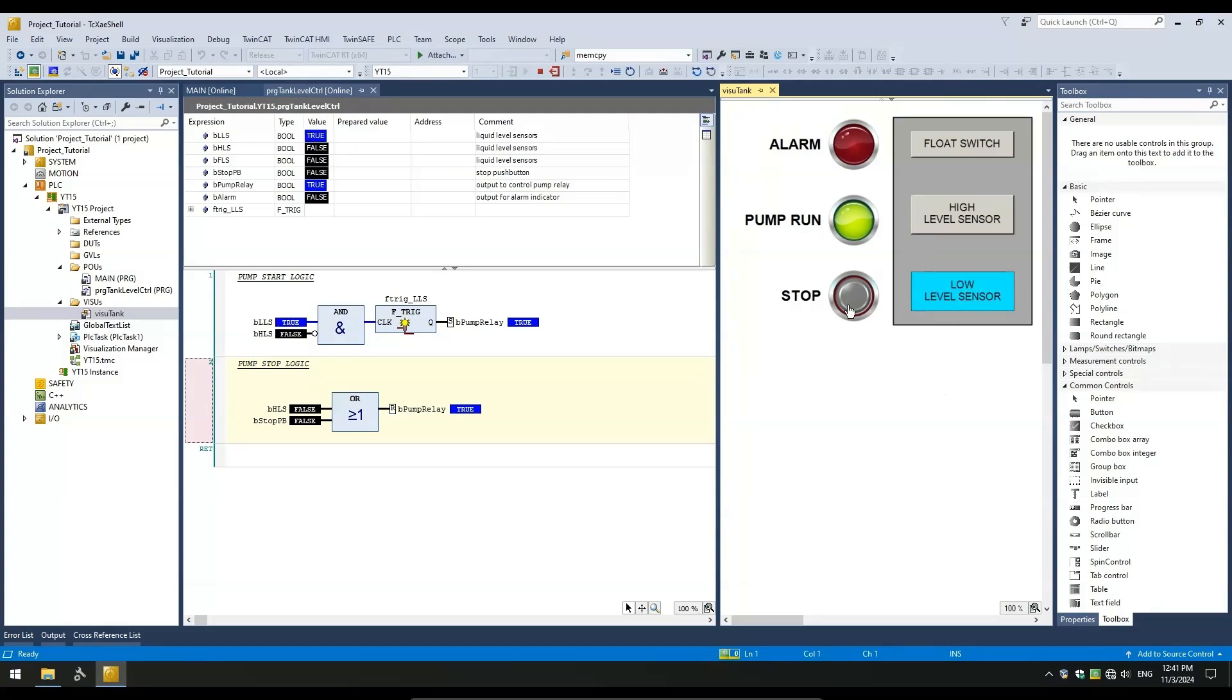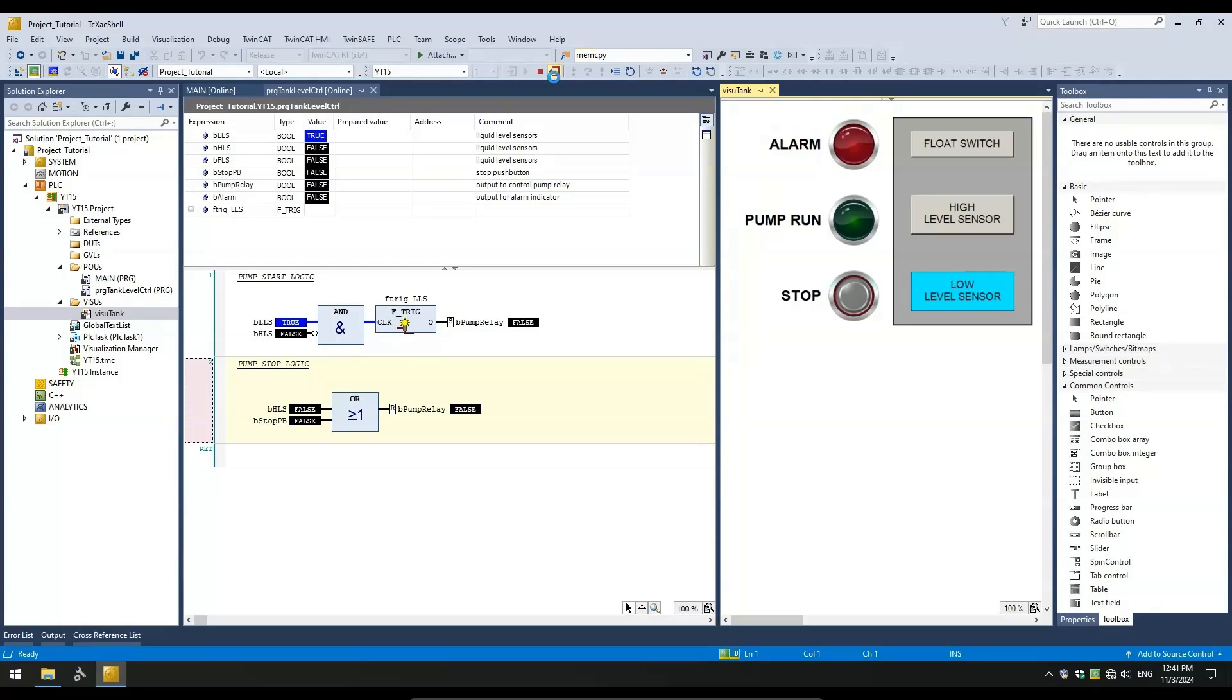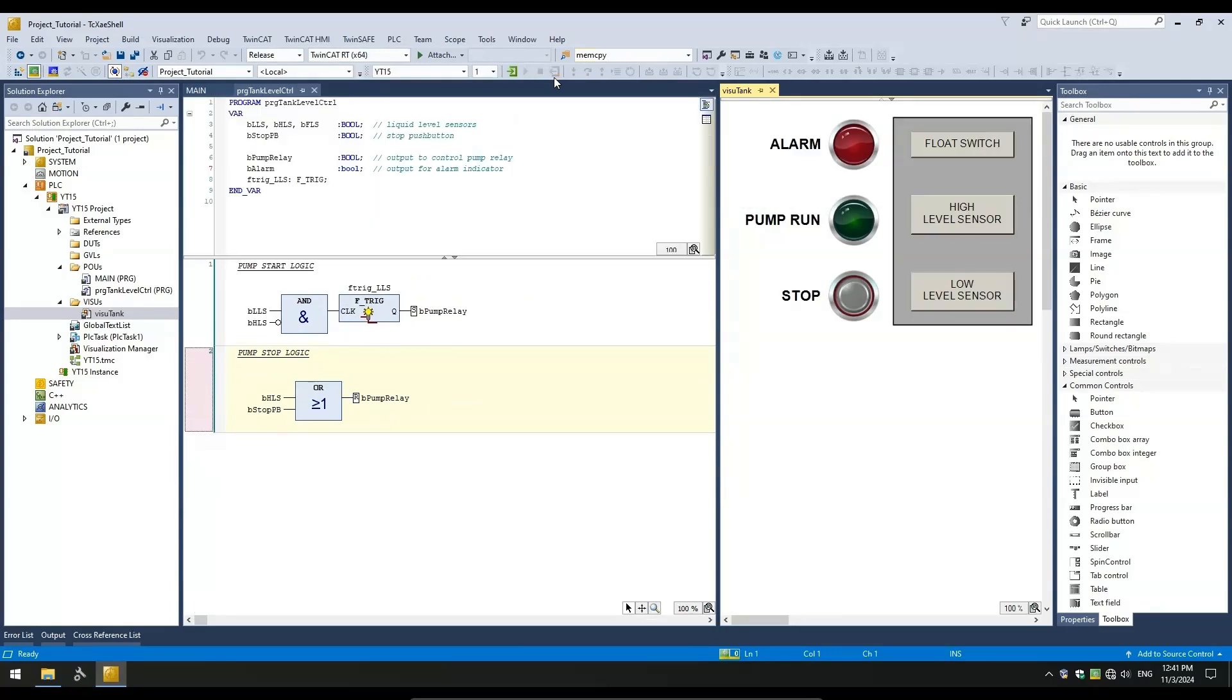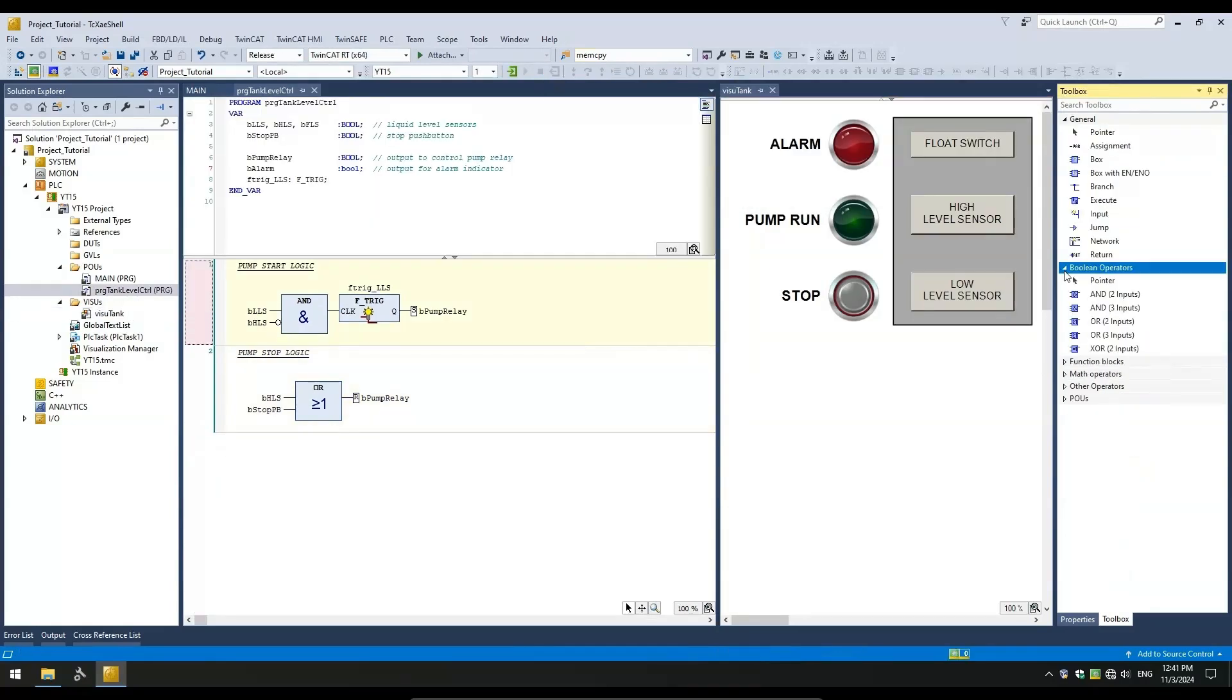Let's test the stop push button, which can be used to manually interrupt the filling by shutting off the pump. However, after the pump shuts off, there is no means to manually restart the pump. Let's modify the pump start logic to restart the pump when the stop push button is toggled off.